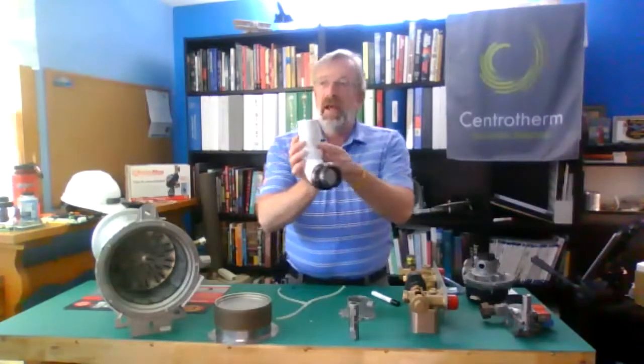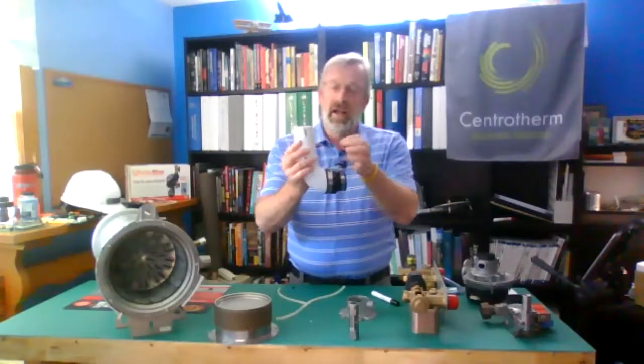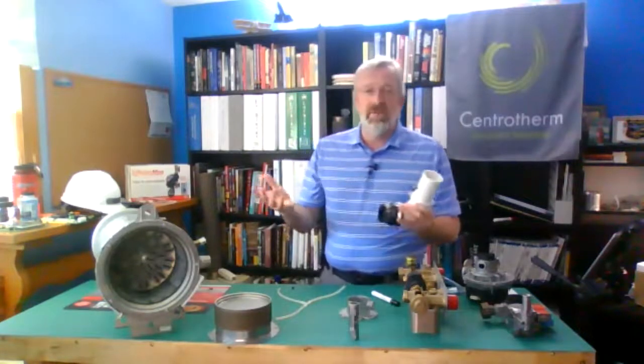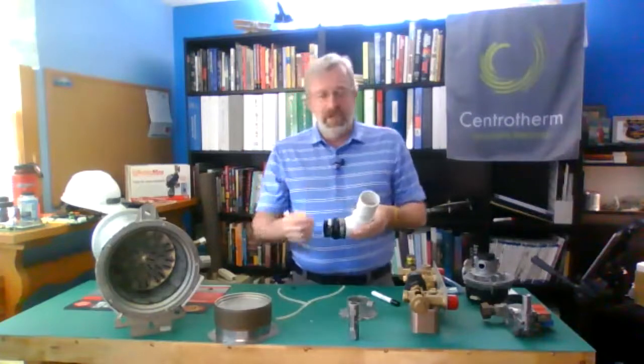The other thing I want to clean, this fitting right here. So this barbed fitting, take that hose off of it, and again, just run an Allen wrench. I think that's a 1.5mm Allen wrench. Just to make sure you clean anything out. It's a brass fitting. I've got some flue gas recirculation. I get a little moisture in there. That could get a little crud on there. I just want to clean it out. That's a good thing to have as part of a PM.